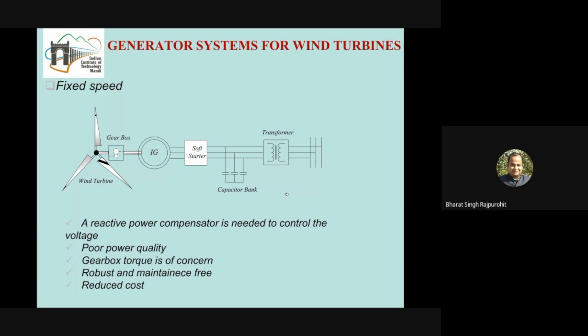Fine. But as per the new grid code, which we will discuss, reactive power supply is also required from renewable energy. So such a scheme may not be good enough to meet the grid code. This is one of the inputs we can see. Otherwise, this scheme is very popular, very robust, very economic, and has a long life with very good connections to the grid. This is known as a fixed speed system because it operates in a very narrow band of speed range, and it does not have a wider speed range. That's why it is known as fixed speed.